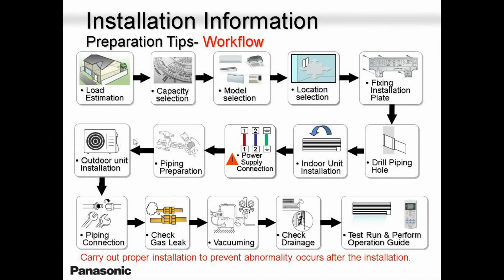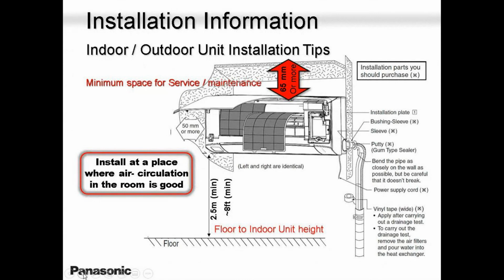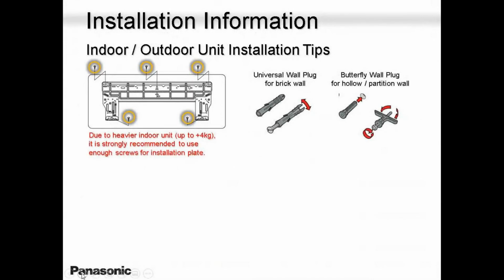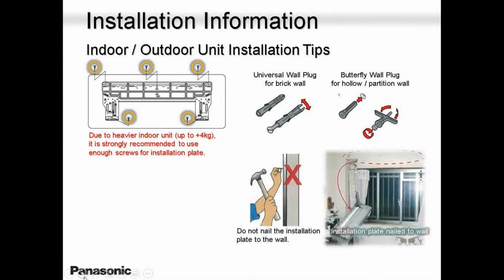Then when you're installing this back plate, we call it the fixing installation plate or the back plate, make sure you have enough screws. Make sure you have enough fasteners, and make sure it's nice and firm. That way you will avoid rattling. And make sure that your drywall is completely square, nice and flat. Failure to do that, my friends, and in less than 9 months you will get a call from guys complaining about the fan motor or the blower wheel making a lot of noise. That's because of the backplate not being straight. So please make sure your backplate is nice and firm.